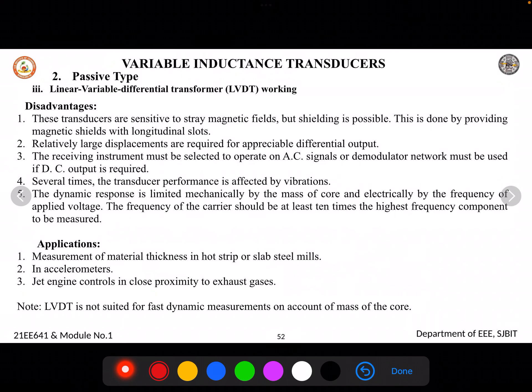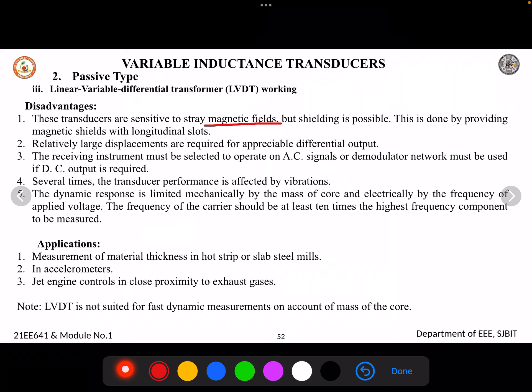Some disadvantages: LVDT is sensitive to stray magnetic fields, so it cannot be used where shielding is not possible. Additionally, the receiving instrument must be selected to operate on AC signals, or a demodulator network must be used if a DC output is required.